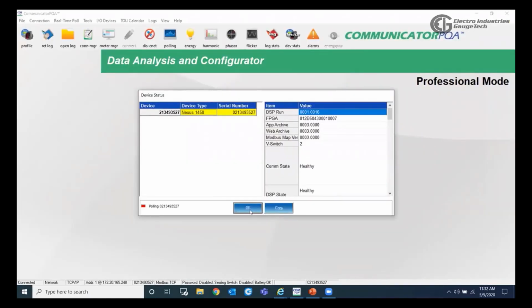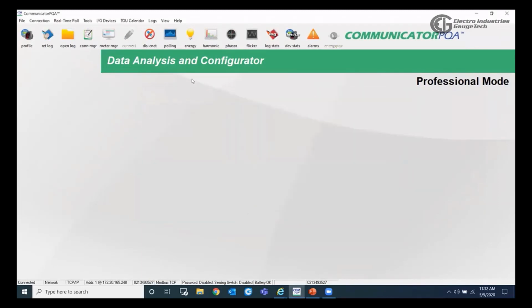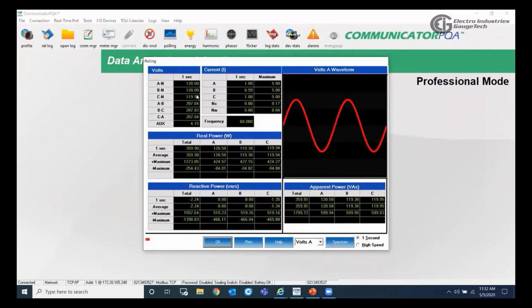Okay, after connecting here, we will start with the polling screen. On the polling screen, we will be looking at voltages, currents, and power readings. As you can see, these are the voltages line to neutral and line to line, and the currents, frequency, and the power readings. We also have the option to view the waveform for the voltages, and we can choose any of the other voltages or the current. And we have the option to choose between spectrum and waveform.